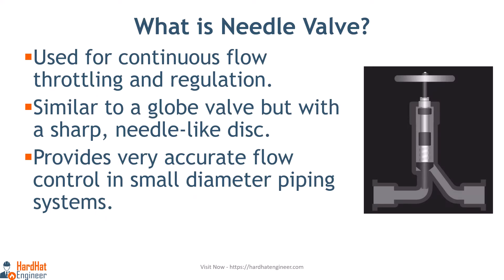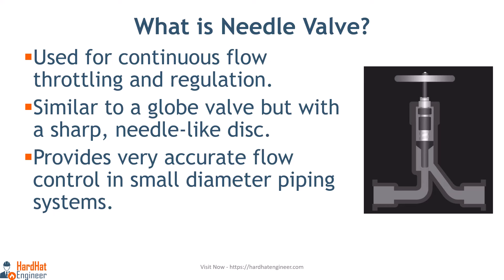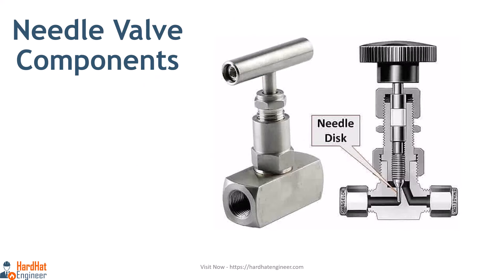What is a needle valve? A needle valve is a manual valve used where continuous flow throttling is required for regulation. Needle valves are similar to the globe valve in design, with the biggest difference being the sharp needle-like disc. They are designed to give very accurate flow control in small diameter piping systems. They get their name from their sharp pointed conical disc and matching seat, as you can see in the image.